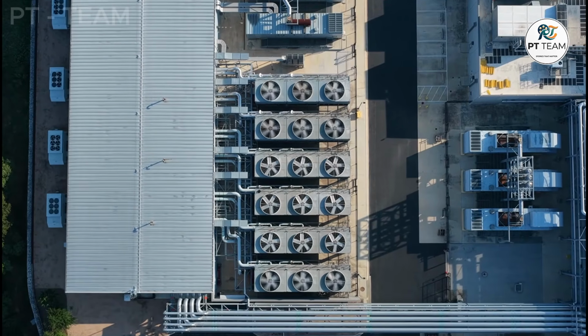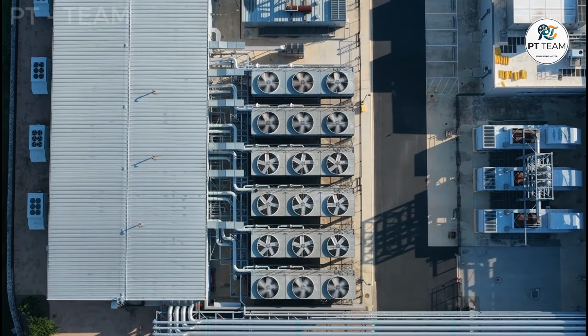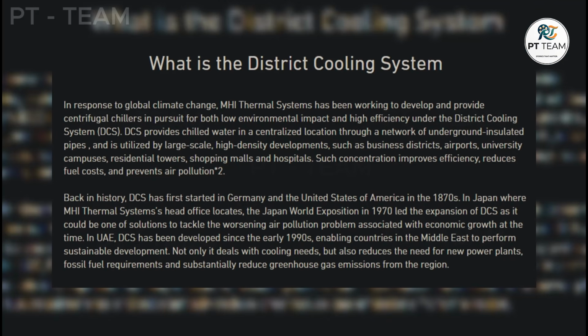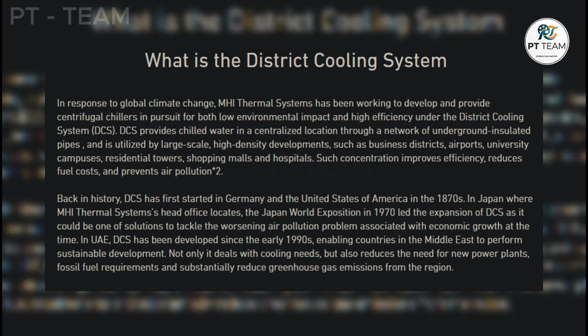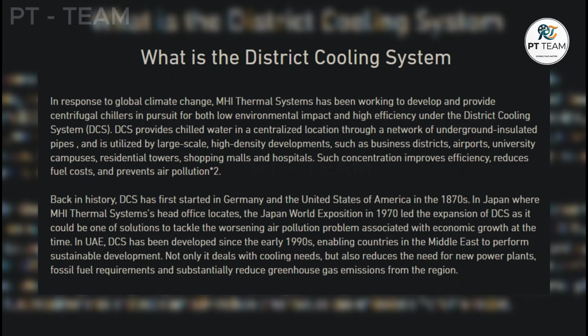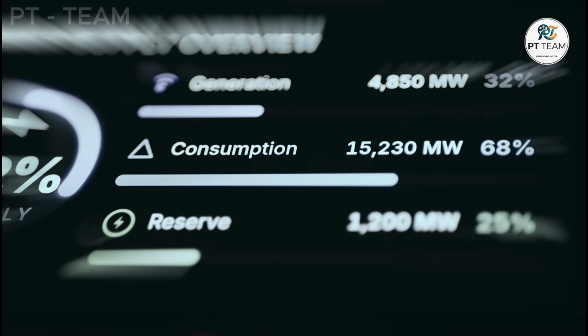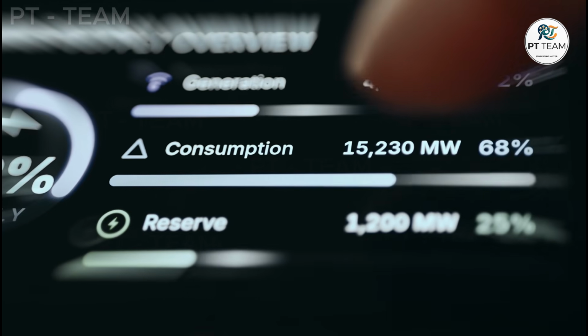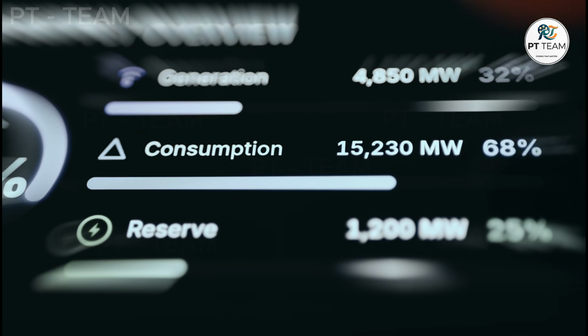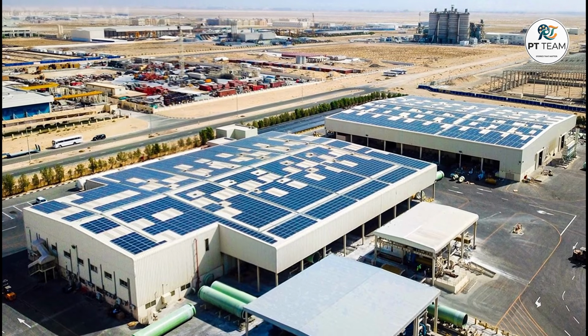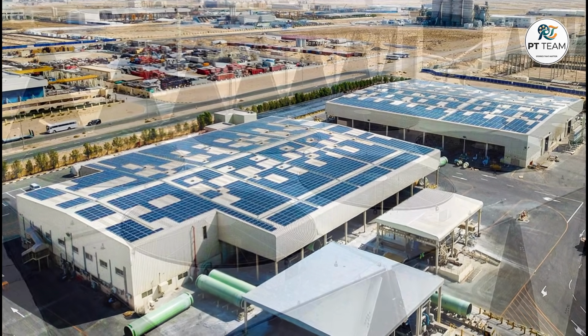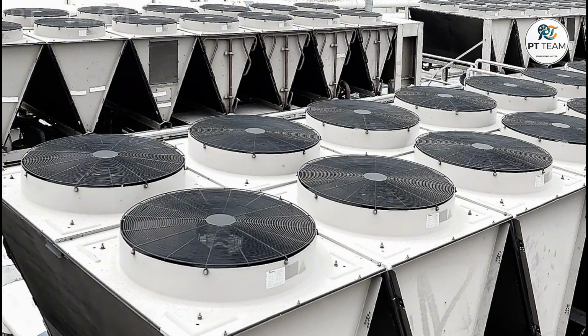District cooling is not necessarily a foolish engineering choice. Official statements from Dubai authorities claim that district cooling can reduce cooling-related energy use substantially. Some claims highlight energy reductions approaching 50% compared with conventional standalone systems. A centralized plant can support massive thermal storage and optimize operations in ways that an isolated rooftop chiller simply cannot.